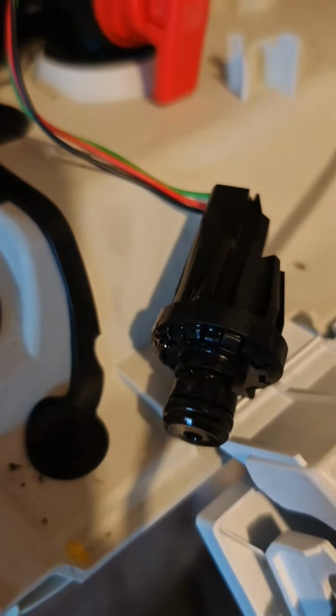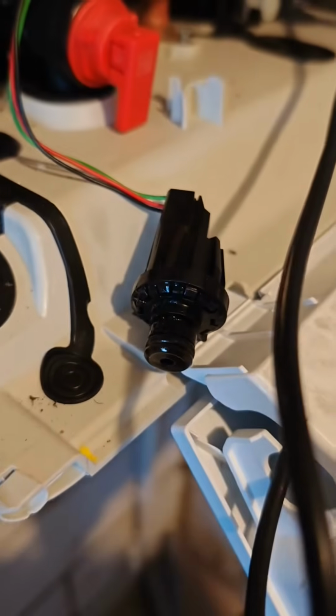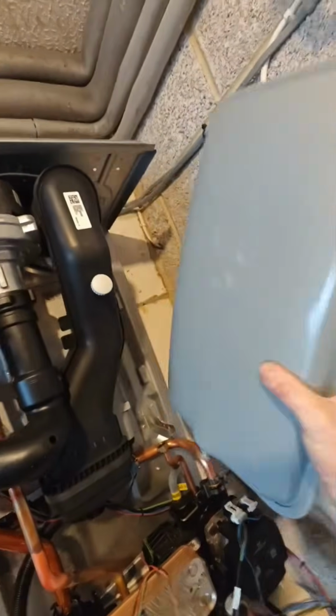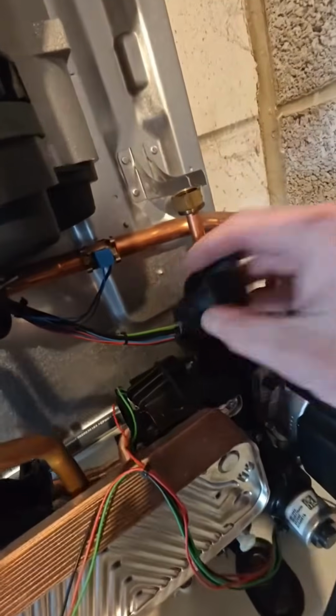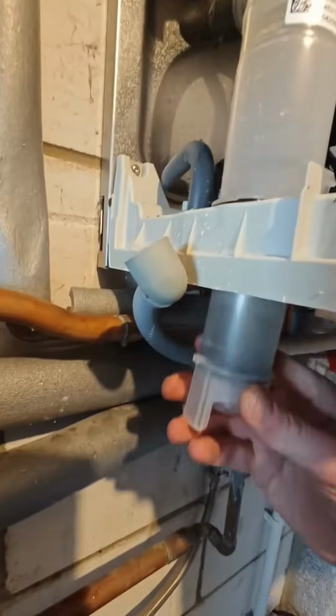Now I can remove and clean the pressure sensor. Now this is a major cause of breakdowns on these boilers, and just cleaning it on the surface prevents a lot of problems. Now I can actually remove the vessel. Next is this part, the automatic air vent, which will be cleaned. Condensate trap. Now I can clean out all the pipework as well.